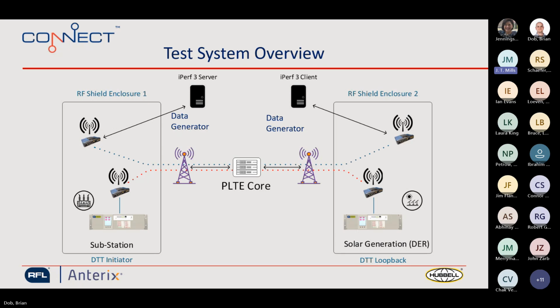So we tried to simulate: if I have a substation and I need to send a signal, what would that look like? In addition to that test, we simulated background data. We didn't just wirelessly connect these devices and only send direct transfer trip. We also added noise generators or data generators on both sides to simulate a common flow of data and packet capture on both ends, so that we could see what a real-life scenario would look like. This was all done in our lab, to simulate a faraway substation and a DER site connected and sending direct transfer trip signals to each other.